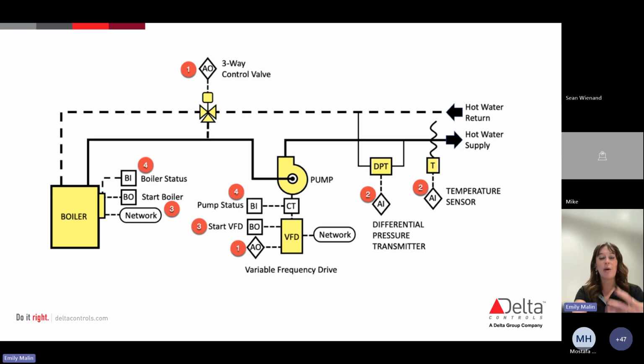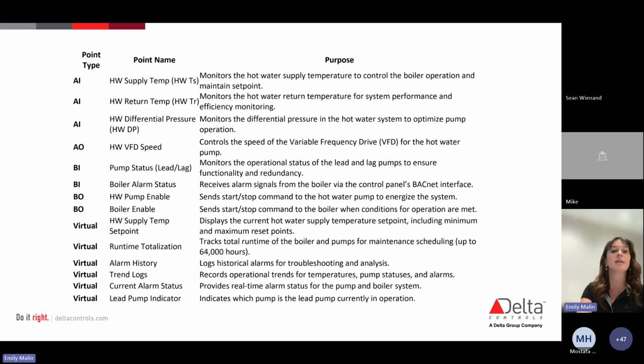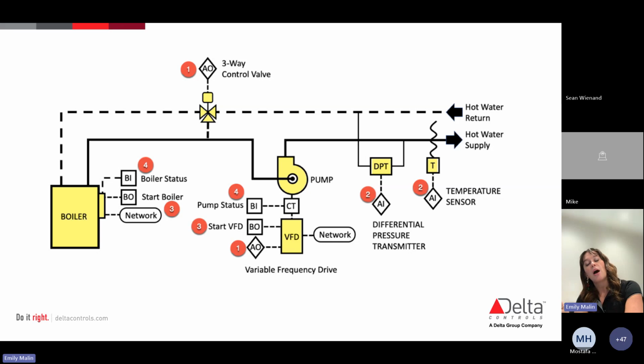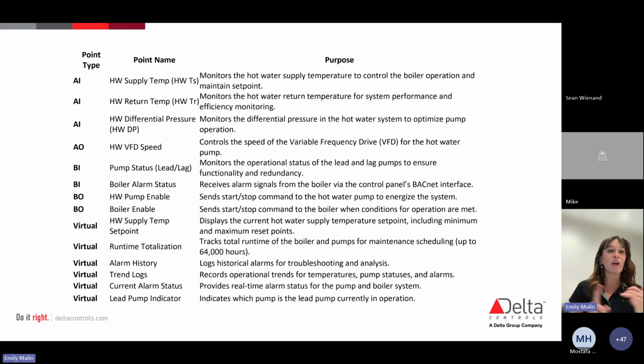So that's really all we're talking about here, just getting to that point where we now have our points list. That schematic was a really good one to build up our points list. We can see on here, as we talked about before, we have our analog inputs, analog outputs, binary inputs, and binary outputs. What we talked about again is just the basics of a sequence of operation. But when we talk through our controller, we now have a set list of inputs and outputs that we might need on a controller. So if we're going to use an advanced application controller to control this boiler system, we know that we're going to need 5 inputs and 3 outputs. So again, we start to think about selecting the correct controller for this application, knowing what we now know, in order to heat up the space in our room, right?